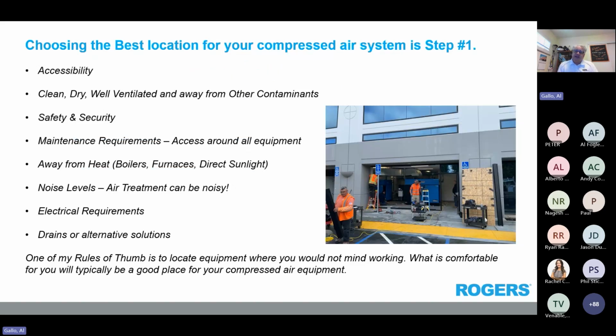But step one is always choosing the best location for air equipment: the compressor, the drying equipment, the air treatment, the tanks, the reservoirs, all that sort of stuff. So we want to look at accessibility. Can we get our equipment in there? Do we have access to it? Do we have room around the equipment to navigate, to service it, to install it, to run the piping? So we always want to see about 3 feet all the way around pieces of equipment. I don't care if that's a compressor or even air treatment.